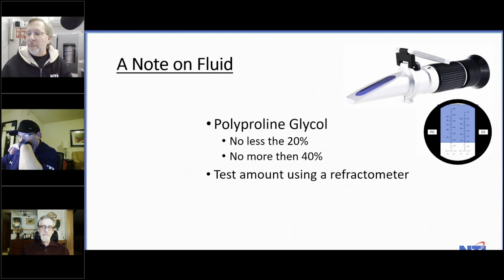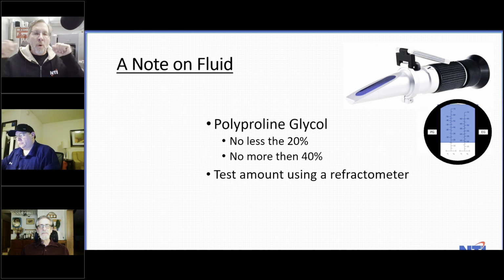So note that. Test using a refractometer, not little bubble testers you use for batteries, not litmus paper to see the acid level - a refractometer. Back when I bought my first refractometer, it was $260. Today on Amazon, I looked it up, $24 I can buy a glycol refractometer for, and it will tell you exactly where you're at. Once you inject it and mix the system, make sure everything's mixed up, then you can test it.